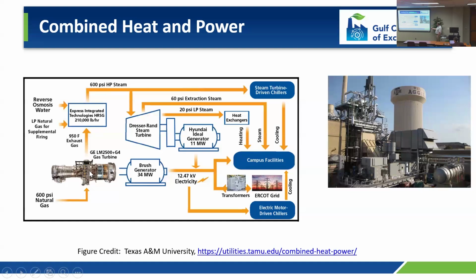We use natural gas in this gas turbine engine, but then we've got exhaust gases which we send through a heat recovery steam generator, commonly known as an HRSG, and generate steam at a pretty high pressure - 600 PSI, higher than what you'd see at most manufacturing facilities. That high pressure steam then goes to a steam turbine, which is hooked to a generator that generates even more electricity. Plus, after we're done with the high pressure steam, we pull out two different pressures of low pressure steam.